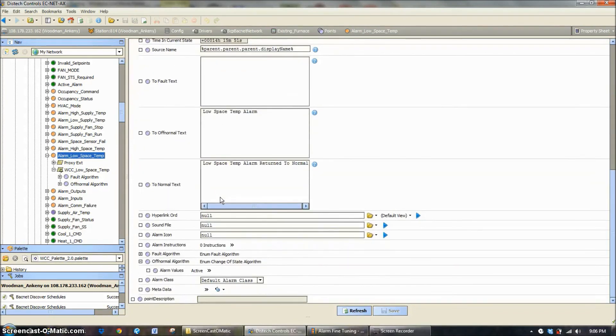The off-normal algorithm is showing when this alarm is actually going to take place. In the case of these enumerated points, there are only a couple of values this point can take on — currently it's disabled, enabled, normal, and active. We only want the alarm extension to go off when it's active, so down here you would select the only item you want it enabled on is active. Now, if you had a boolean alarm, an on-off, or a numeric alarm, you may want your alarm to be active when it's above 80 degrees or below 60 degrees — you'd have a few more options in here to make those kinds of alarm transitions.